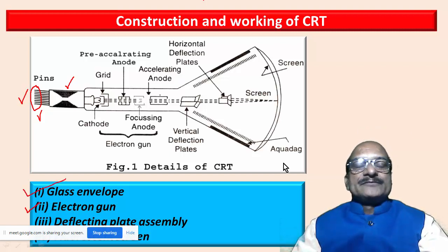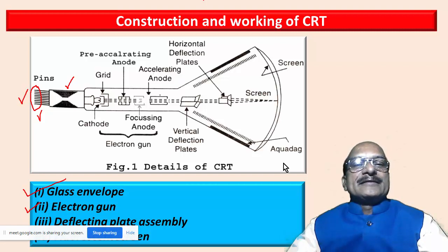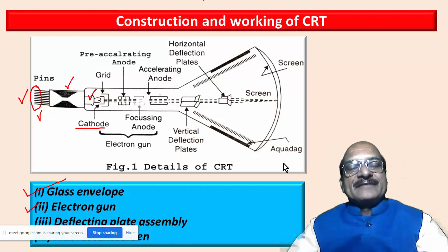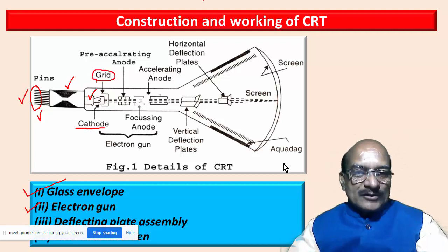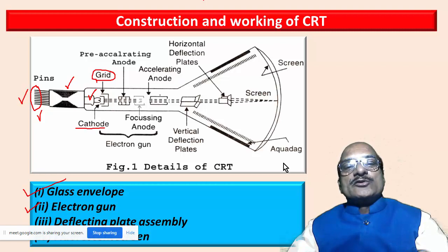The important part of the CRT is the electron gun. The electron gun provides a sharp, well-defined beam of electrons — that is its main function. This electron gun consists of the filament. When we pass current through this filament it produces heat, and that heat is given to the cathode. The cathode is heated by means of the filament, and when the cathode is heated it emits electrons. These emitted electrons are controlled by the control grid, which is given a negative potential.